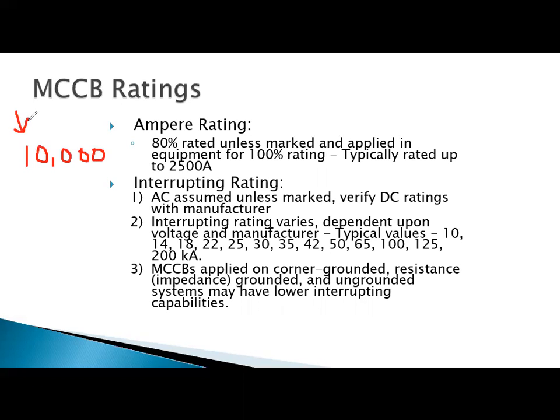Now, when we get to commercial or industrial facilities, we can see that it could be 10,000. These are all kA, so we have to multiply each one of these by 1,000. Or look, it could be up to 200,000 in some facilities. Depending on the size of the transformer, the larger the transformer, the larger my fault current is going to be. So I have to be able to determine what that interrupting rating is.